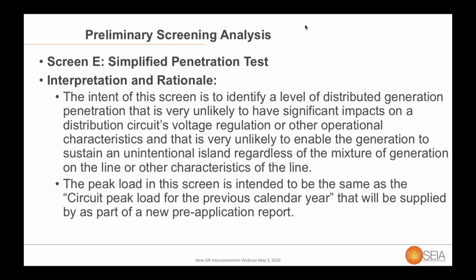And therefore, they took an engineering safety factor of 2, they reduced the 30% to 15%, and at that level, they argued that you would very likely be below the minimum load on the circuit, and none of these other types of concerns would be an issue. The peak load, because of the importance of this, is one of those places where the pre-application report will first be of great use to you.